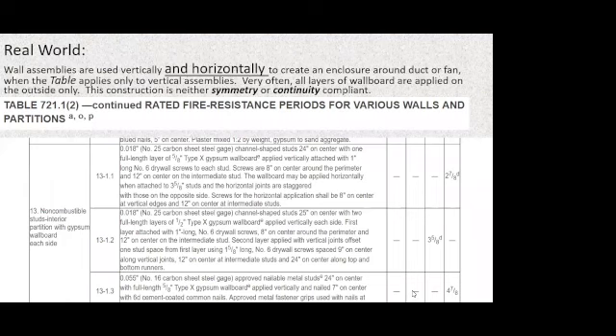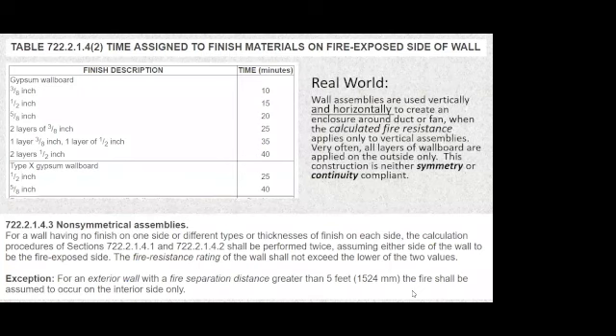And for your architectural friends who might say 721.1 allows me to build things out of drywall, I advise you to look at the top of that table. It says partitions. That means vertical orientation. You do not get to put those in the horizontal orientation. 722, the finished table, says the same thing. And you'll notice in both of these cases, the paragraph that describes the use of the table talks about non-symmetrical assemblies. We're talking about the ability to test both sides. You don't get to put it all on one side.